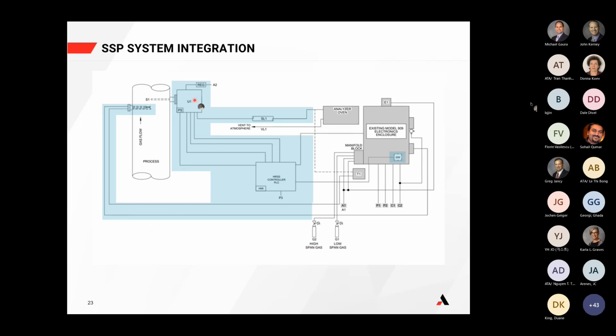Typically, we would integrate the flow sensor and the RTD with the actual heated probe tube portion of the probe. A lot of that will just depend on flange size and nozzle diameter. We can also do it as a separate entity, as is shown here. So often this will actually run up here to the probe head, and as I said, the pitot tube and the RTD would be integral as part of the probe assembly.